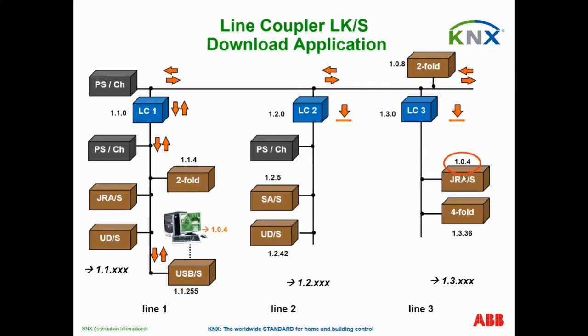This is a common issue I see on sites where switches have been installed on wrong lines. There's all sorts of different reasons for it, but usually it's devices have been installed, presence detectors are in the wrong areas, switches are in the wrong lines, etc.